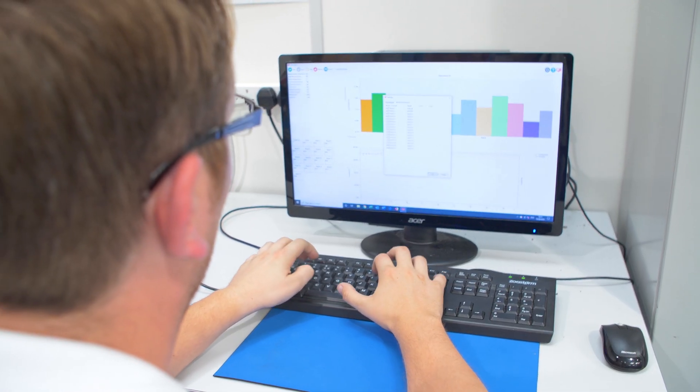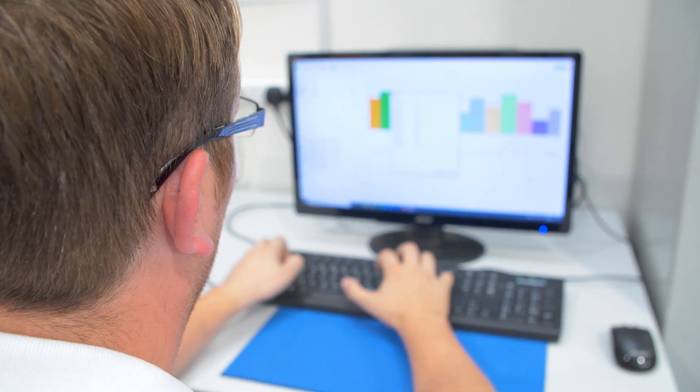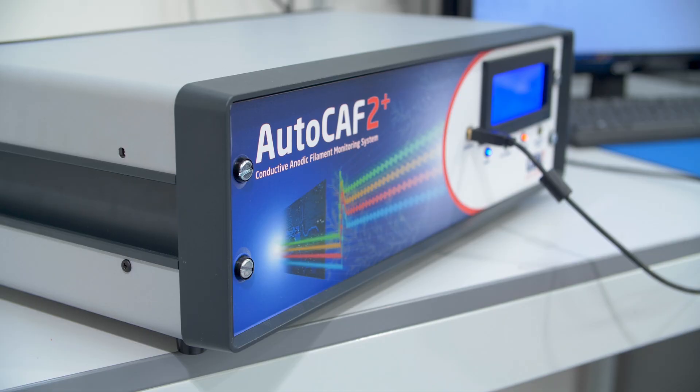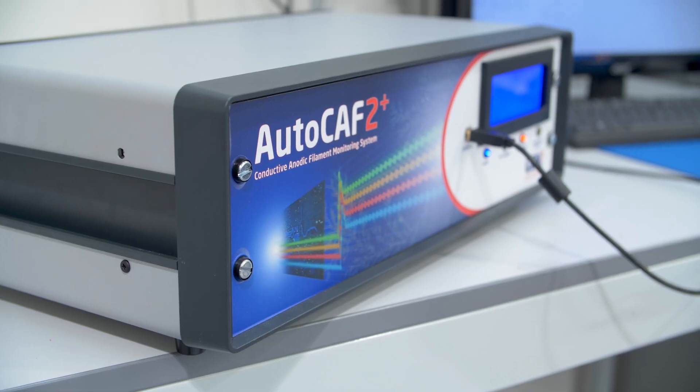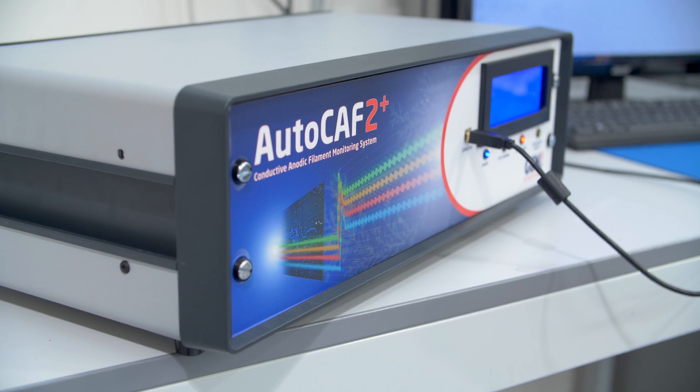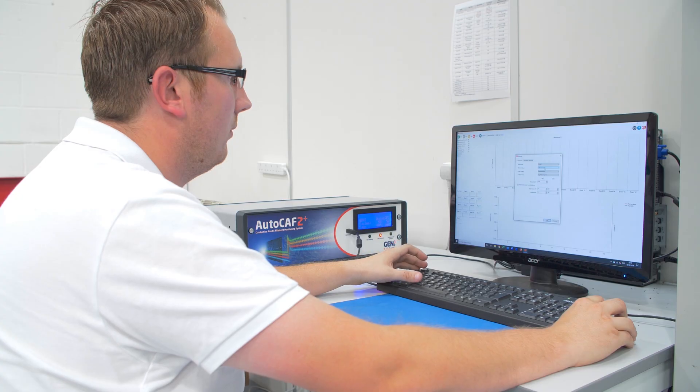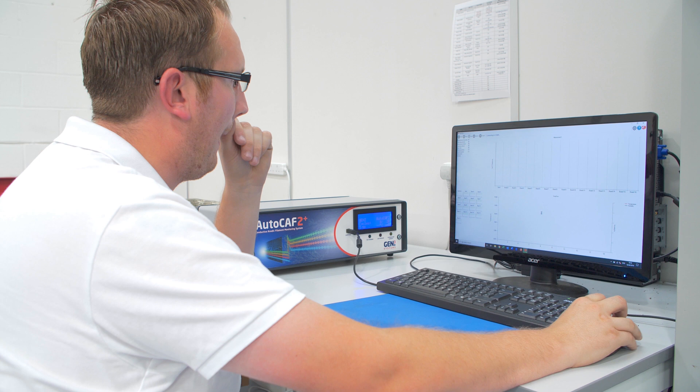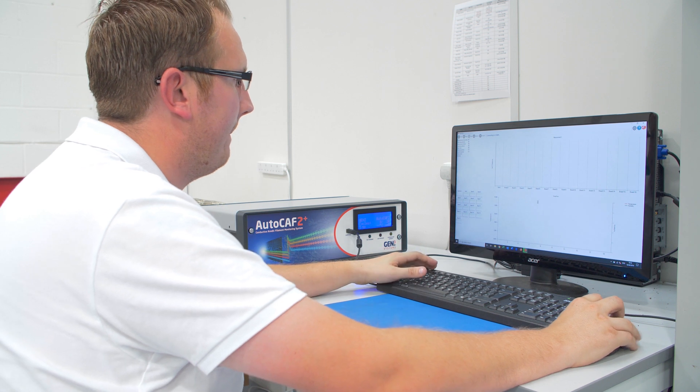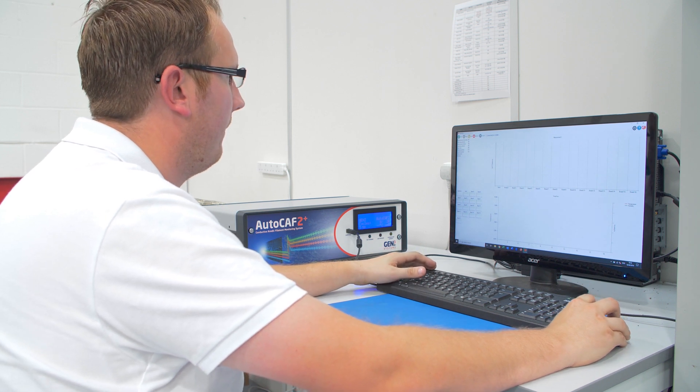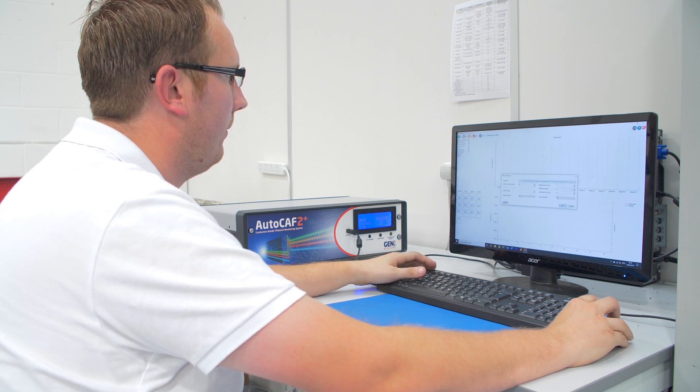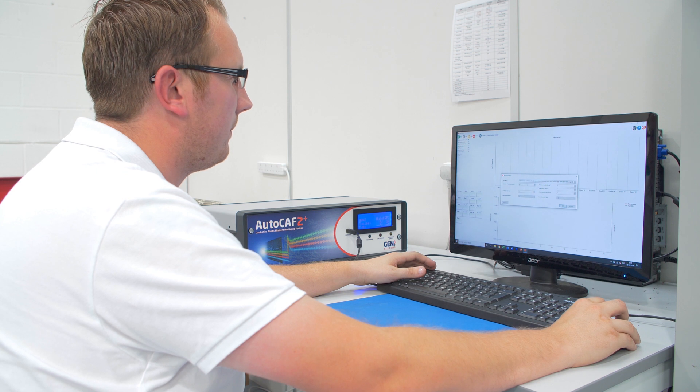In a normal setup you would have a laboratory with an environmental chamber and you would hook up to a rack in the chamber, then you would go through the IPC standards in terms of humidity and temperature over time. The current readings will be registered. You must use DI water that has to be very, very clean, as pure as it can be, and obviously maintain cleanliness inside the chamber with no water or contamination.